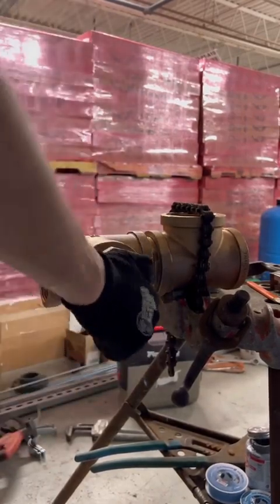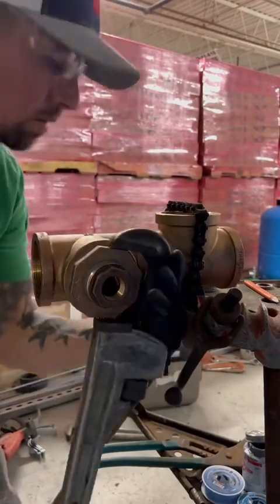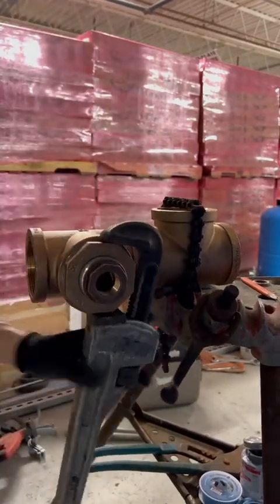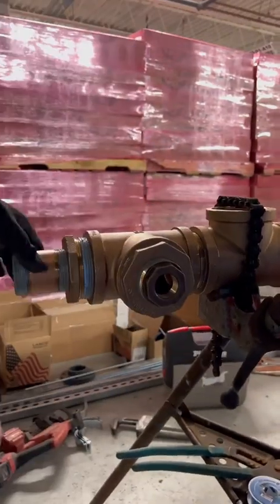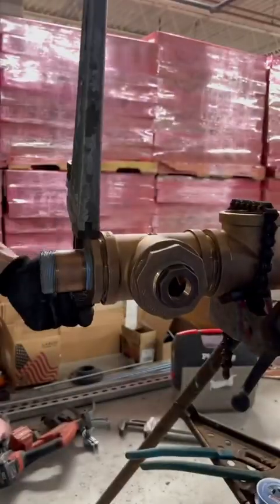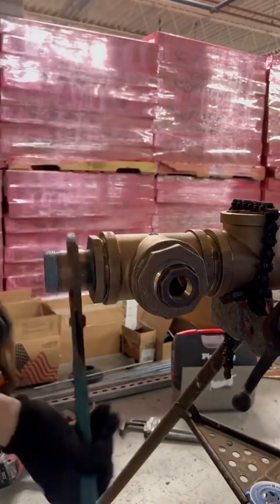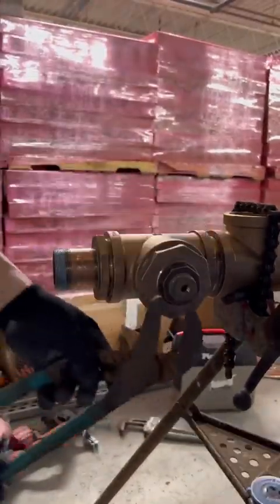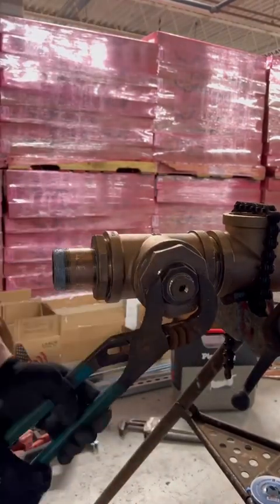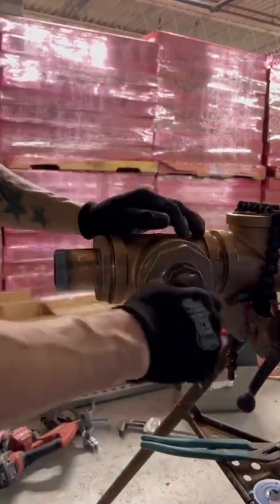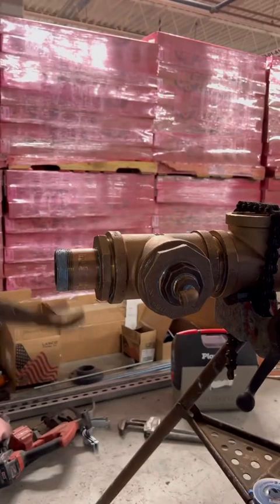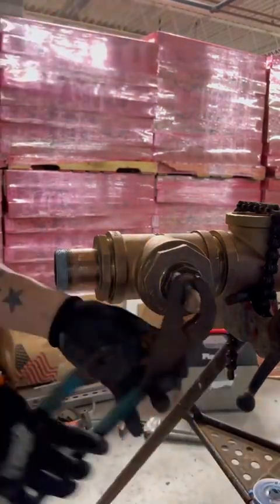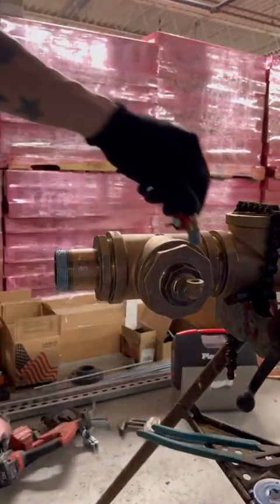But enough of that, let's get to this installation. So these are 3-inch tees, and I needed to bush down to get to a gauge, which is 1/4 inch, and a well, which is 3/4 inch. So by following the specs where they wanted brass, that's what I bought, and the way to get down to that was 17 bushings later. And yes, that is the large pair of channel locks that were the closest things to me, and this is a 1/4 inch 90 that I'm using that large pair of channel locks on. So come at me, bro.